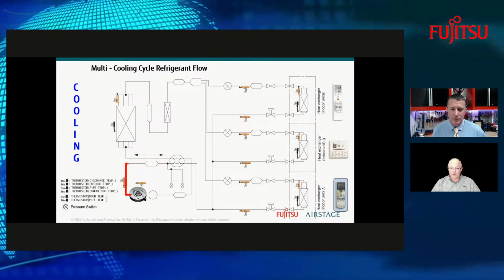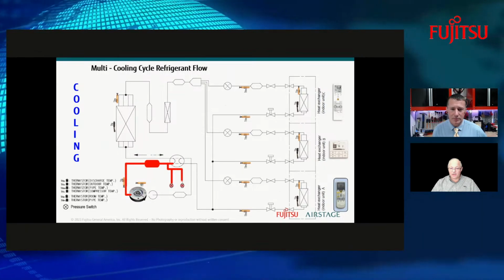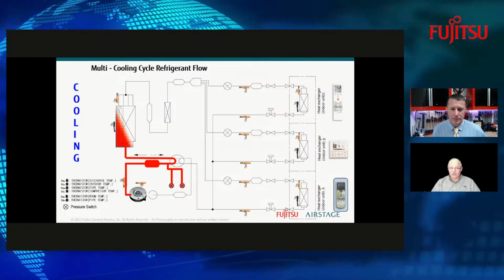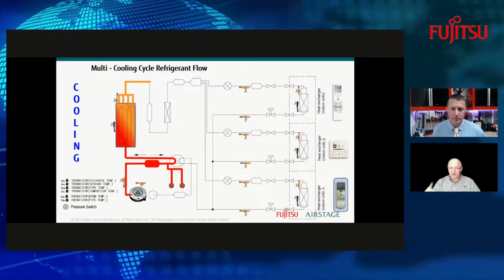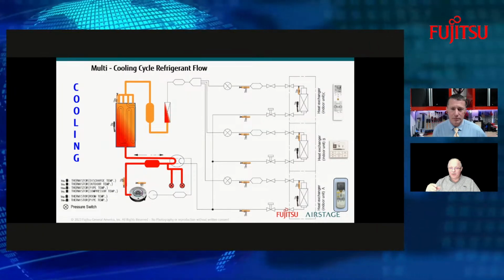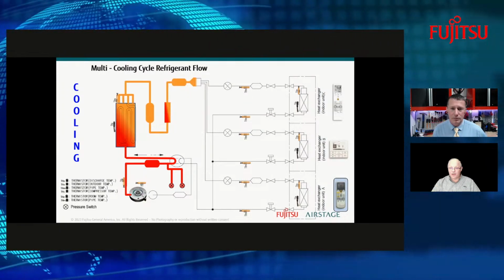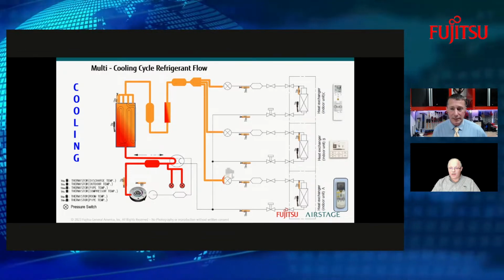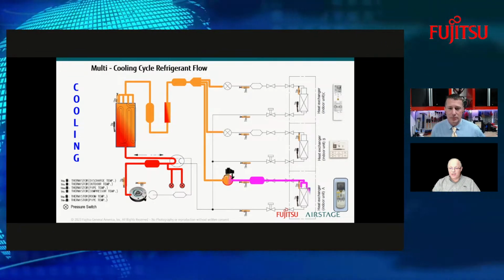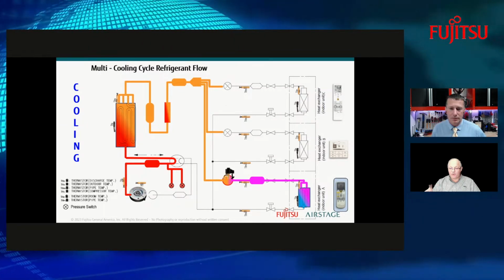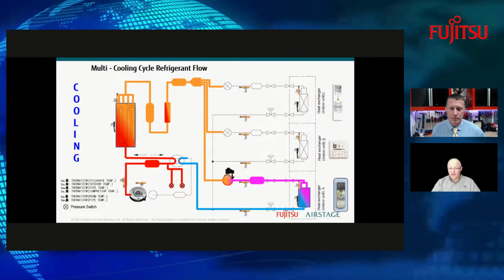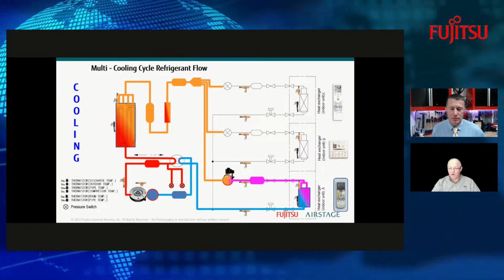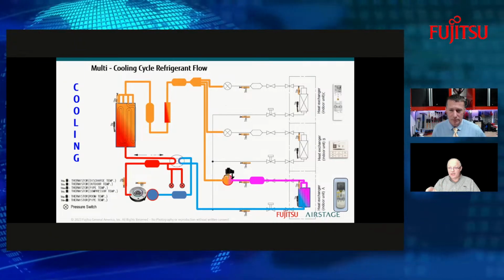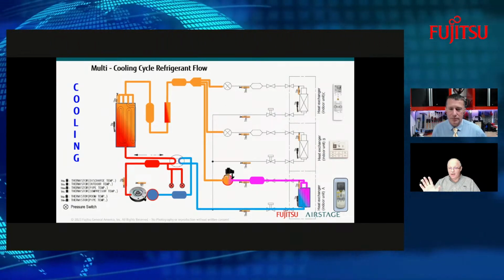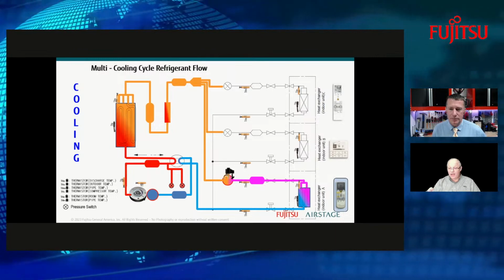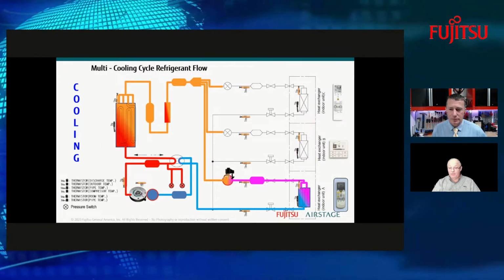So this is how the system is going to operate. One of the mini split indoor units tells the system to start up. So my compressor starts up. I go through the outdoor heat exchanger, and now I'm going to send some subcooled liquid to all the EEVs in the outdoor unit. Now, the one inside on unit A called for it, so I've got refrigerant going through it. It's going back through the 4-way outside and back to the compressor. Now, this system's just going to keep running. Let's say the other 2 are just fine and don't need anything. This system could run, satisfy zone A, and then cycle right back down and be just fine.